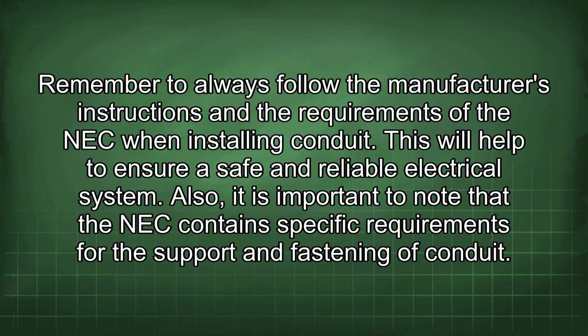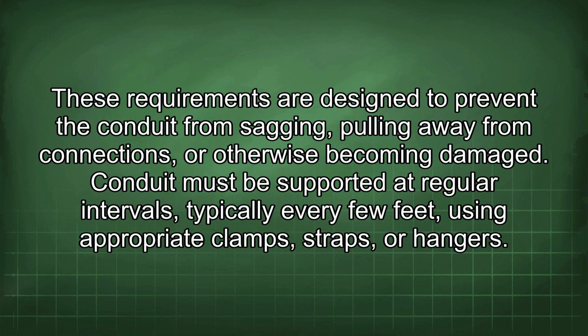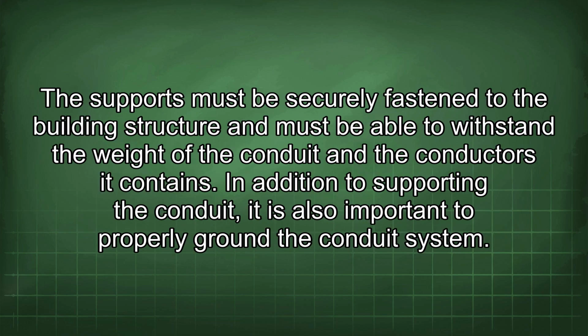Also, it is important to note that the NEC contains specific requirements for the support and fastening of conduit. These requirements are designed to prevent the conduit from sagging, pulling away from connections, or otherwise becoming damaged. Conduit must be supported at regular intervals, typically every few feet, using appropriate clamps, straps, or hangers. The supports must be securely fastened to the building structure and must be able to withstand the weight of the conduit and the conductors it contains.